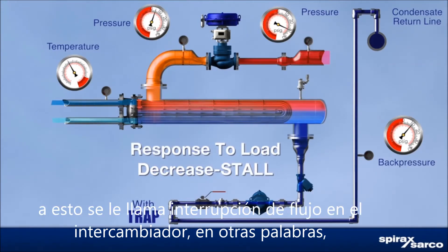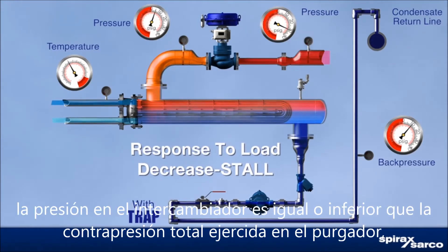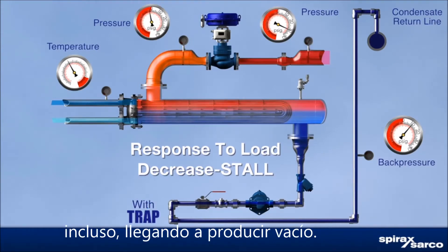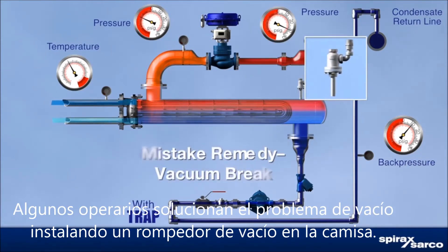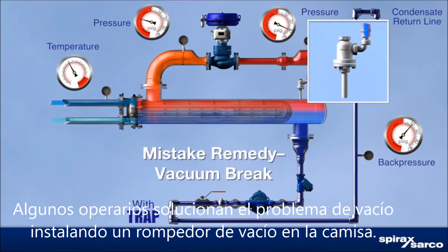In other words, the pressure in the heat exchanger is equal to or less than the total back pressure imposed on the steam trap, sometimes even attaining vacuum. Some operators address vacuum in the steam space by installing a vacuum breaker on the shell.